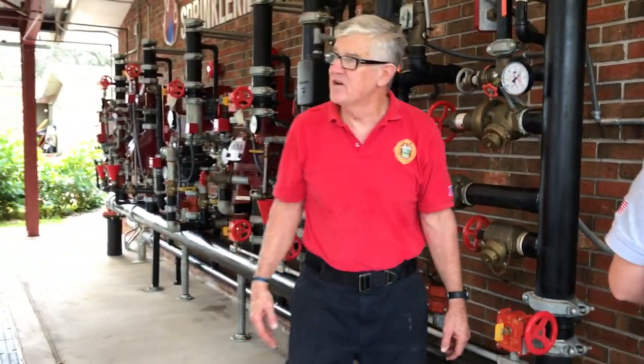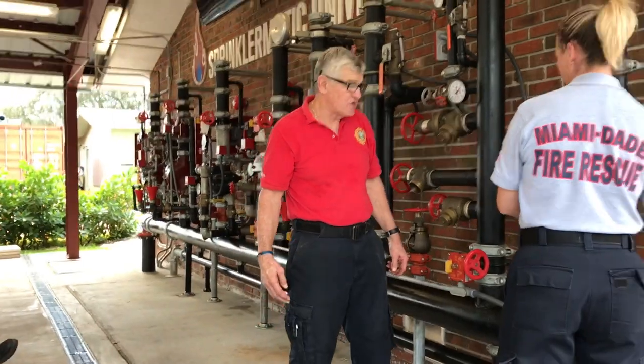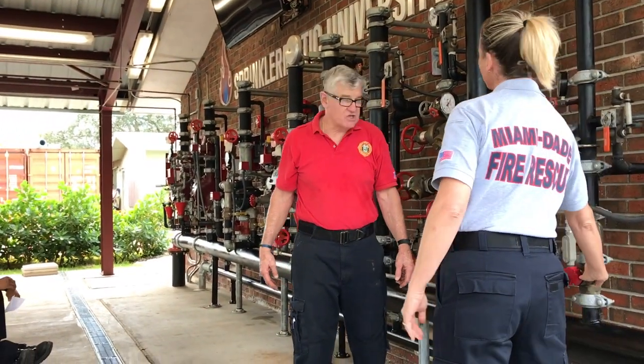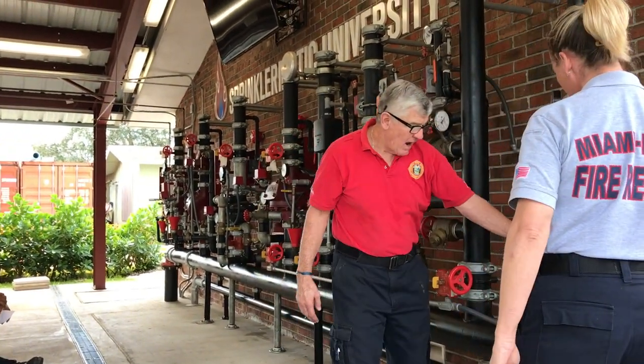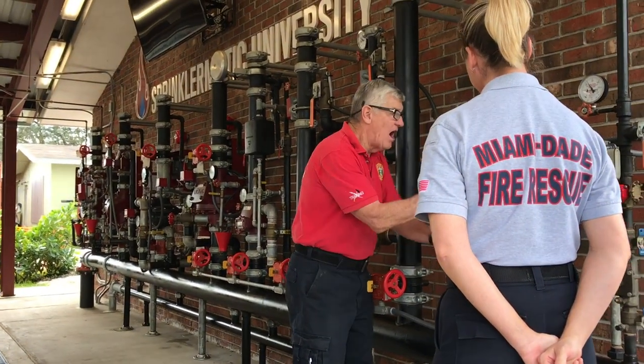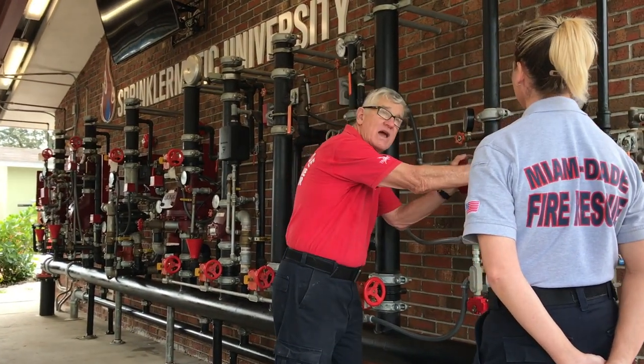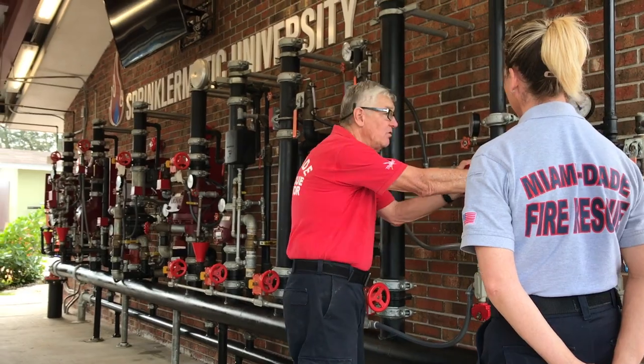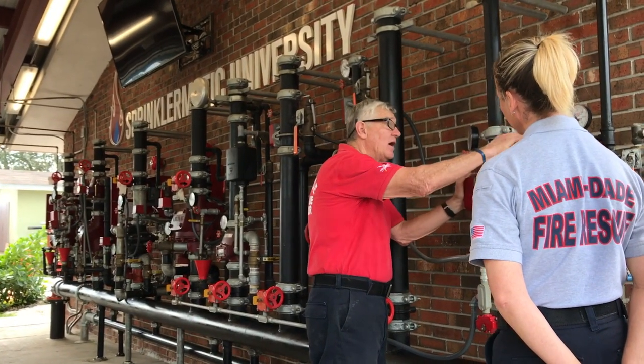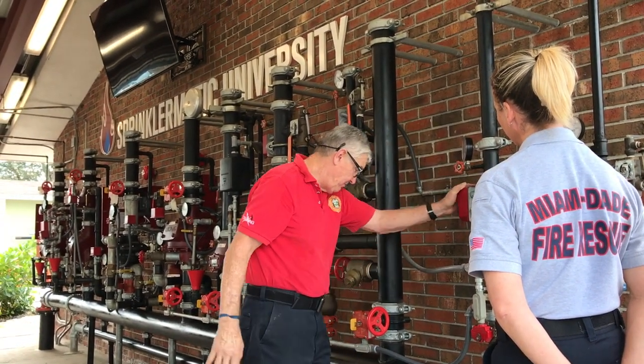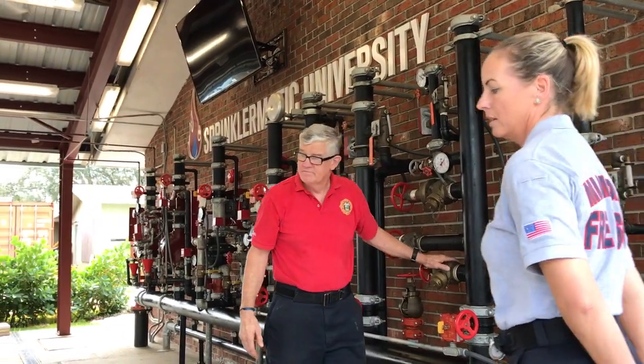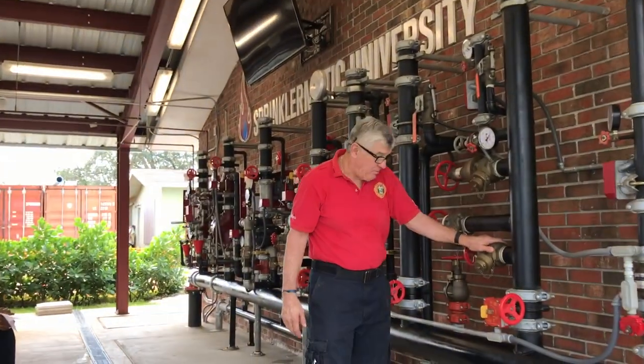13R sprinkler systems are not a firefighter's friend. They're better than nothing, but they do not protect combustible concealed spaces. Again, control valve, check valve, flow indicator, combination flow, drain and test, and relief valve. Thank you, Susie.